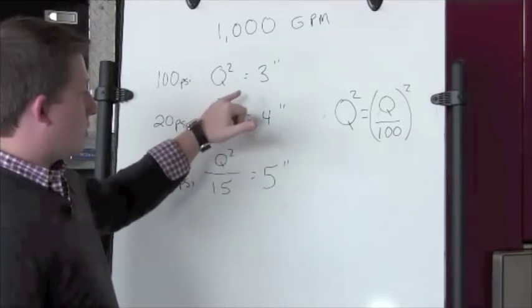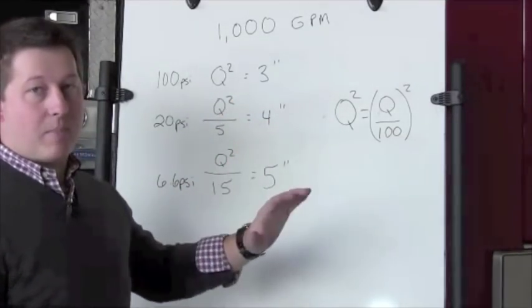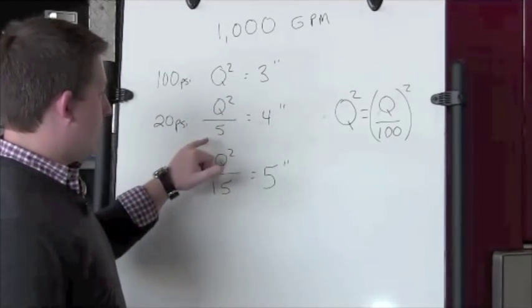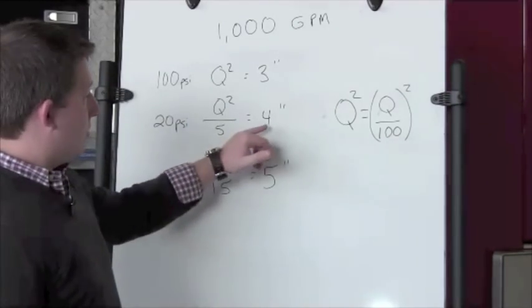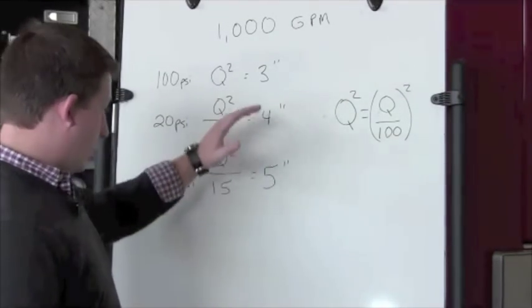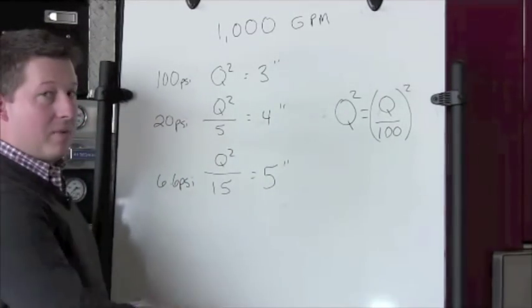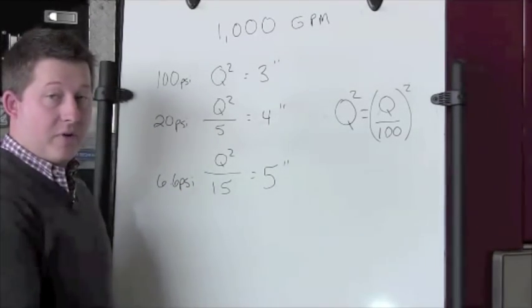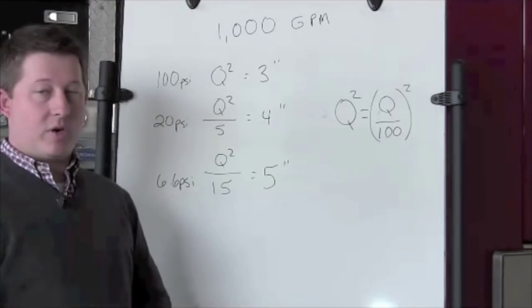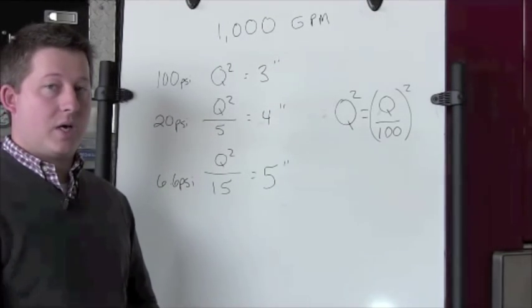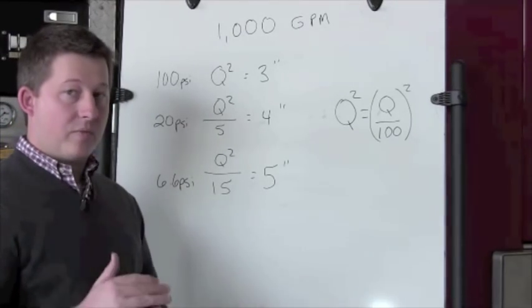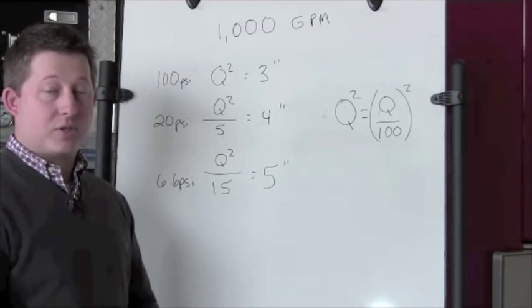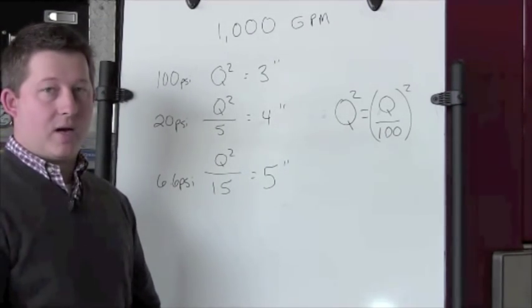When we go up to four inch, Q squared stays the same — 1,000 divided by 100 is 10, so 10 squared is 100. Then 100 divided by 5 gives us 20 psi per 100 feet on a four inch line. When we go up to five inch, we divide Q squared by 15 and end up getting 6.6 psi on the five inch line. So: three inch is just Q squared; four inch, divide by five; five inch, divide by 15. That gives you a good rule of thumb for pressure loss per 100 feet.